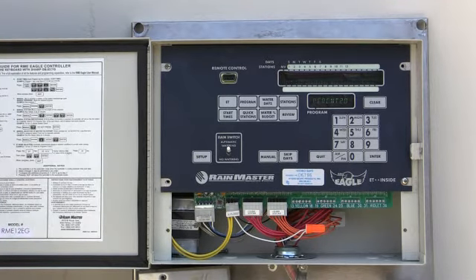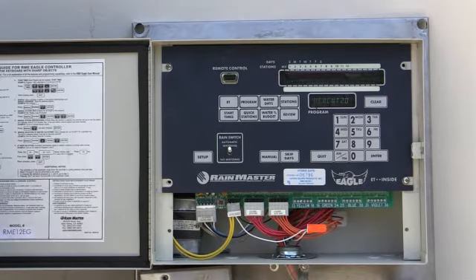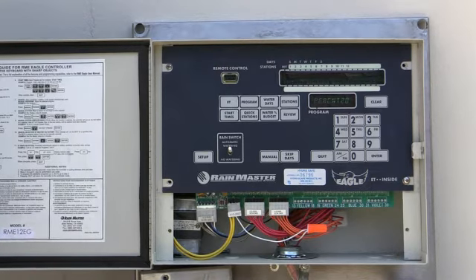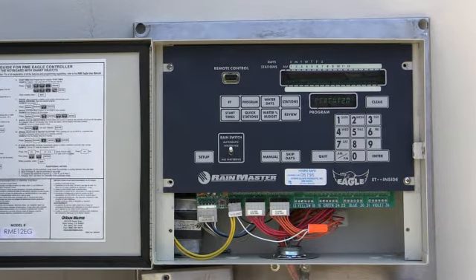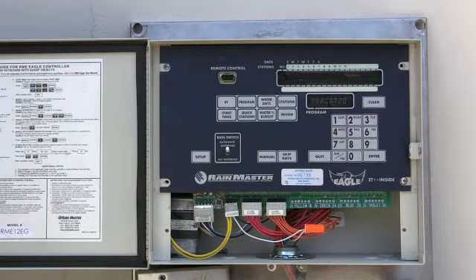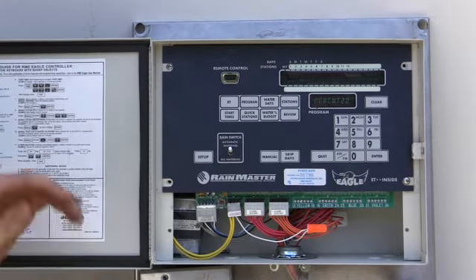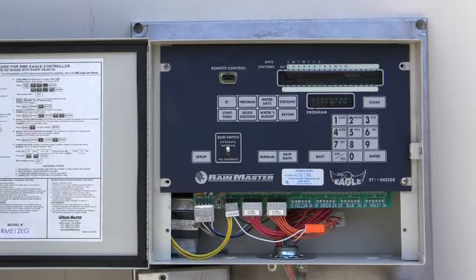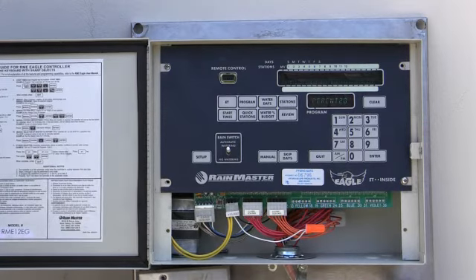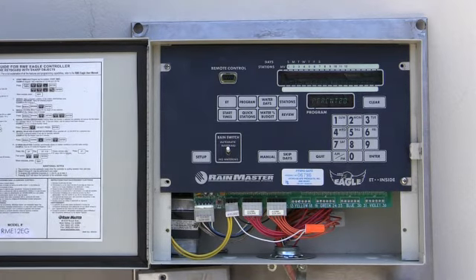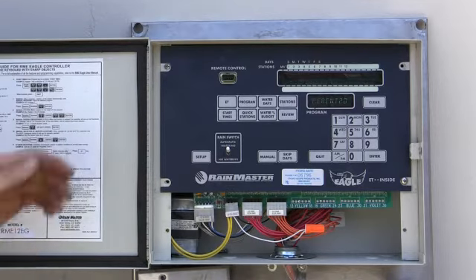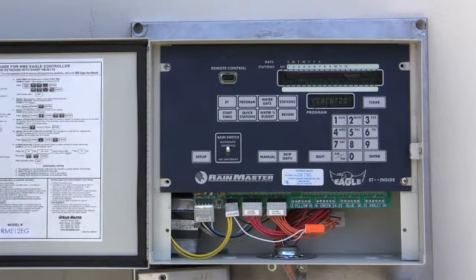This is percentage. At what percentage above my normal flow do I want each station to tolerate before I shut down? So 20%, that's pretty good. That's a pretty good indicator. You can lower that down, and you can get better security if you just break one nozzle off or one head's broken. But that's something you can play with. So this is how you can kind of dial it in.